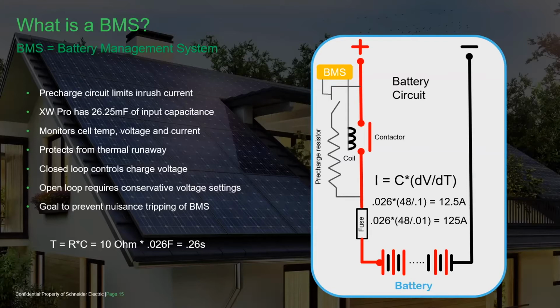With the pre-charge circuit, there's a resistor built in, and your time coefficient is resistance times capacitance. So if you use a 10 ohm resistor, in about a quarter of a second it would reduce that inrush current enough to go ahead and close the contactor and energize the capacitor bank of the Pro.